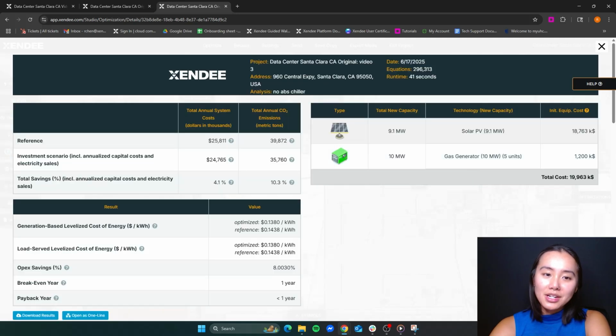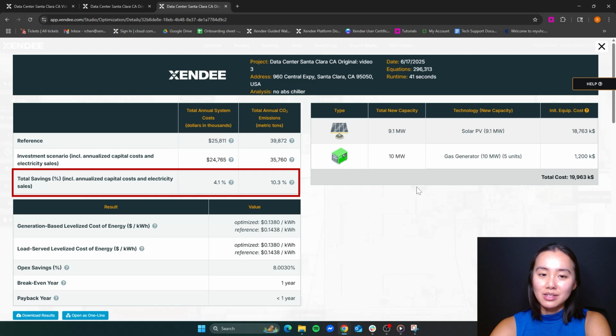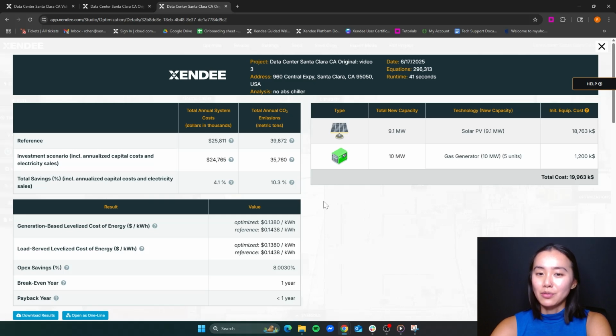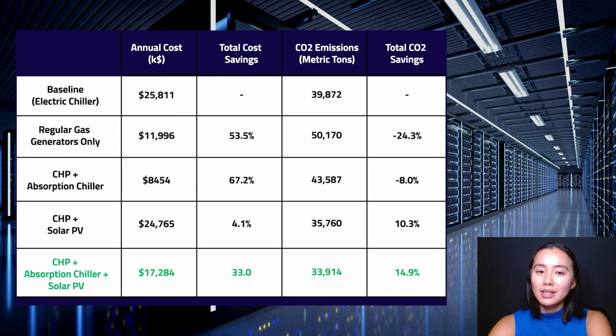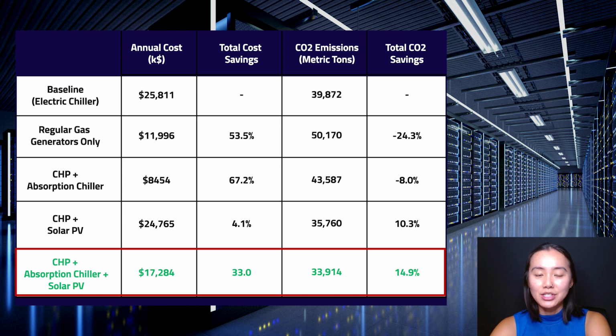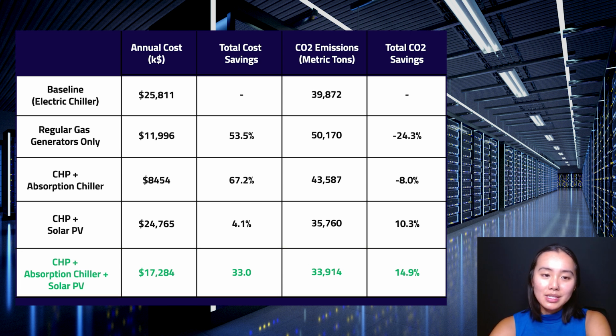A new optimization without the absorption chiller tells us that while only having solar PV and the generator still saves costs and reduces emissions, the savings are much better when there is an absorption chiller present to utilize the waste heat. Here's a table of all the runs that I did, and it clearly shows that the best solution for a data center in California is to utilize CHP, absorption chiller, and renewables, since this reduces both costs and CO2 emissions most effectively.